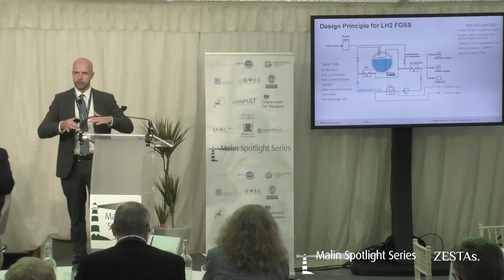So there are no pumps or rotating equipment inside this core technology of a liquid hydrogen fuel gas supply system. It's all driven by pressure. So it's very robust and reliable. No rotating components, no maintenance. The only rotating equipment inside is that we need some kind of a heat source in order to get the vaporization process going. The fuel cell generates a lot of heat. It needs to be cooled. So we can take the energy of the cooling circuit from the fuel cell and exchange that in a heat exchanger unit that heats up an internal circuit. It's the blue circuit, which is a closed loop of a mixture of glycol and water to add heat into our hydrogen vaporizers.